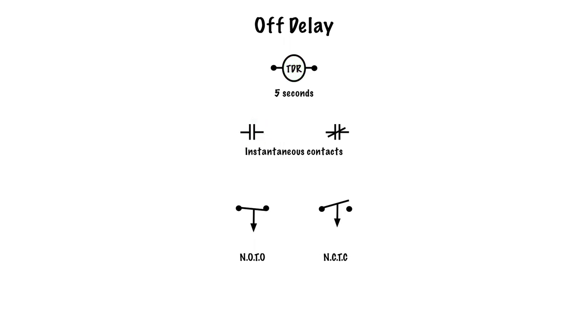When TDR de-energizes, the instantaneous contacts go back to their original state — what was once closed becomes open, and what was once open becomes closed. The magic of the off delay happens with the timed contacts: what was once closed is still closed, and what was once open is still open, because the timing in an off delay begins when the coil is de-energized. It will wait five seconds, then the normally open time-to-open contact will open, and the normally closed time-to-close contact will close.